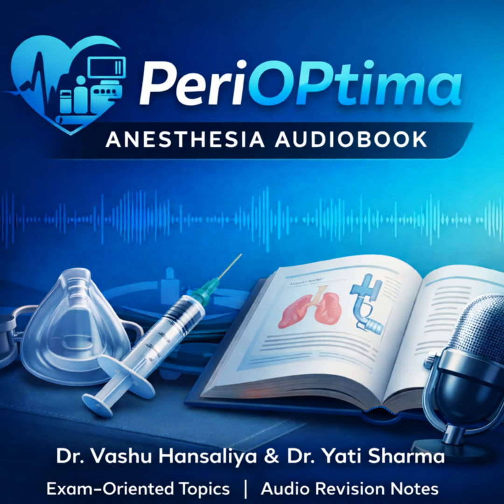So an exam answer has to stress that valve competency is essential. It's everything. A sticking or incompetent valve will let gas bypass the absorber, and that leads to hypercapnia no matter what your fresh gas flow is. Got it. What's component number 3?